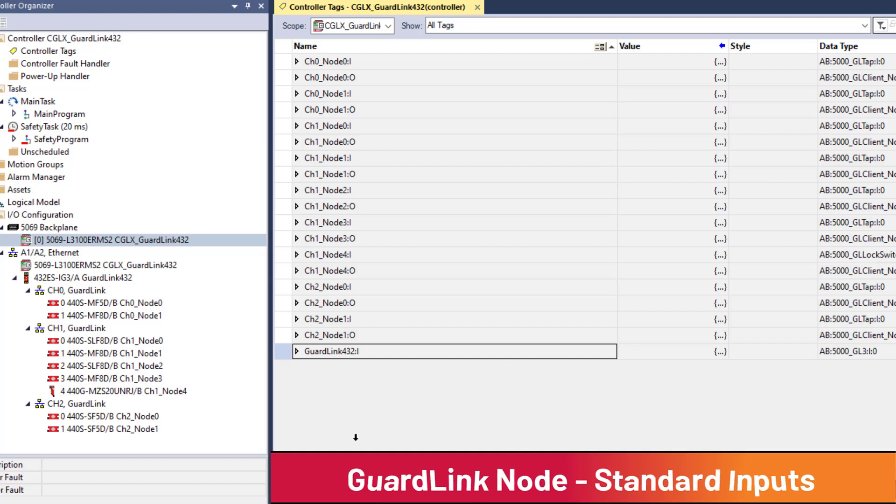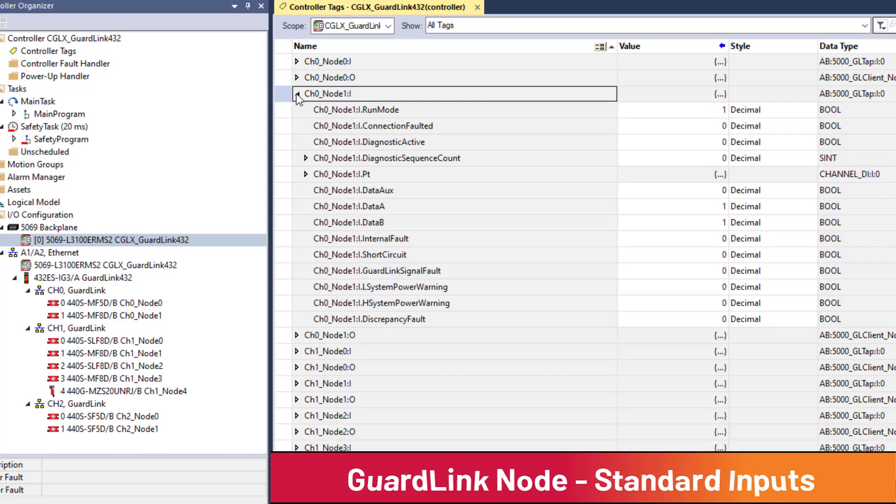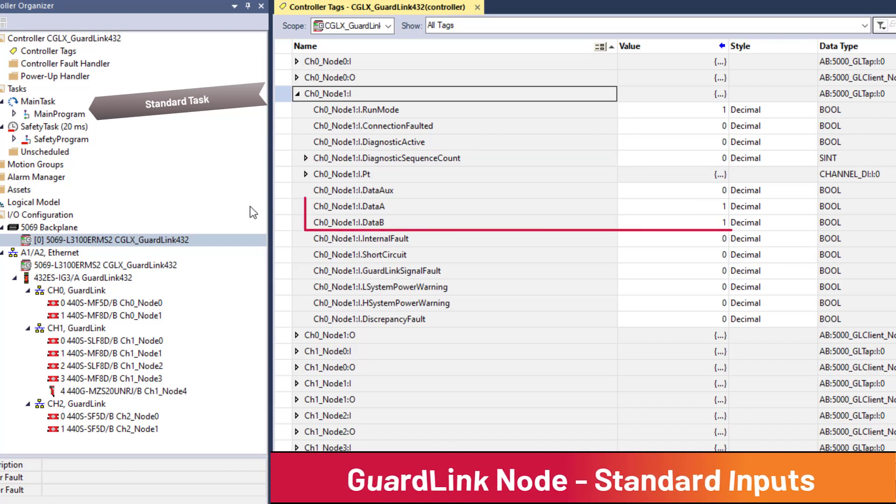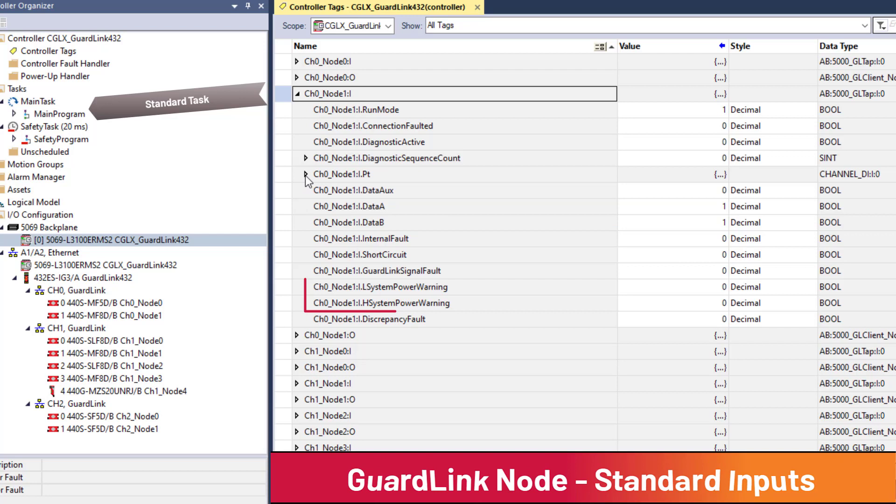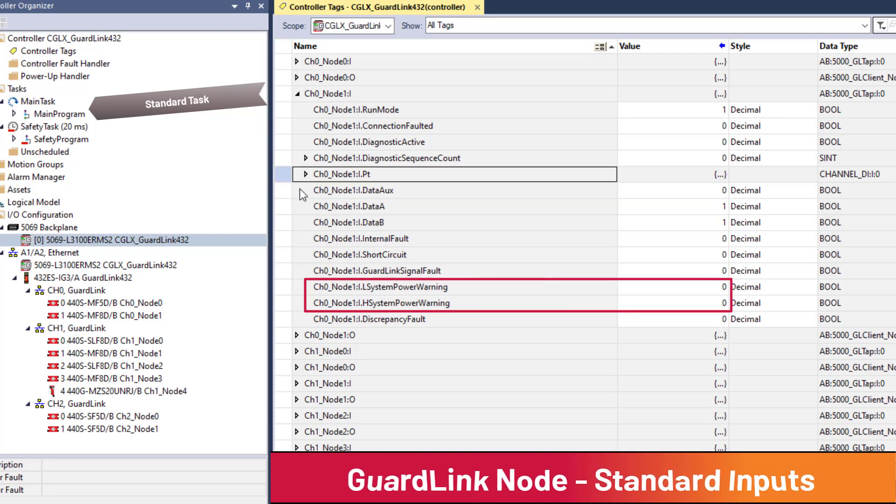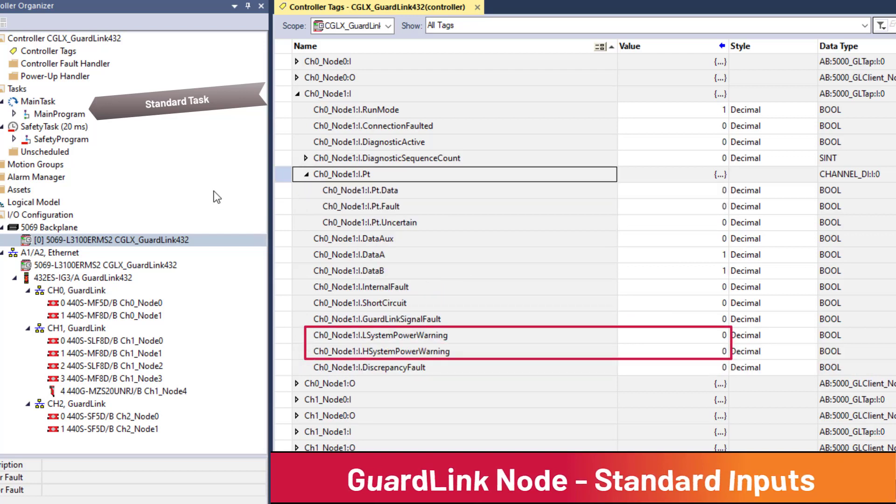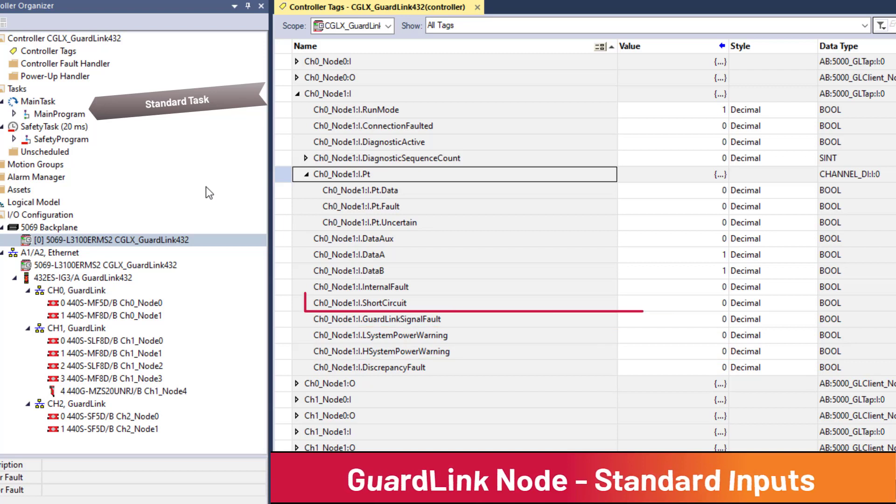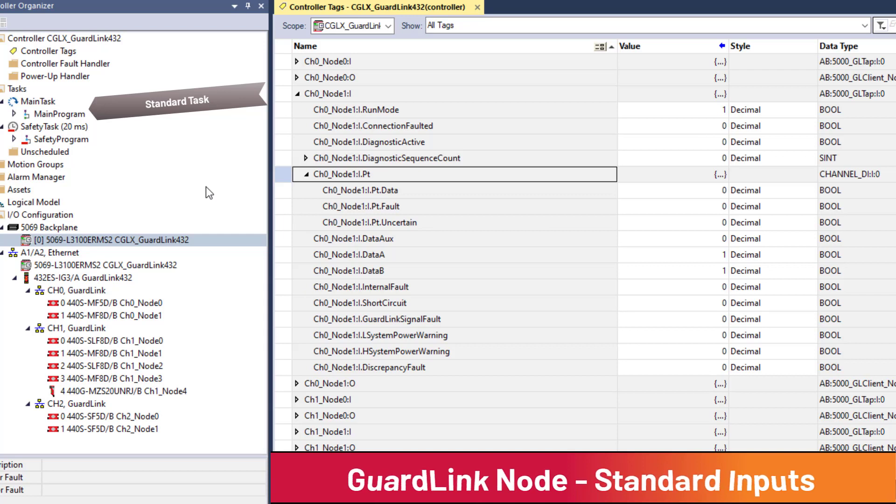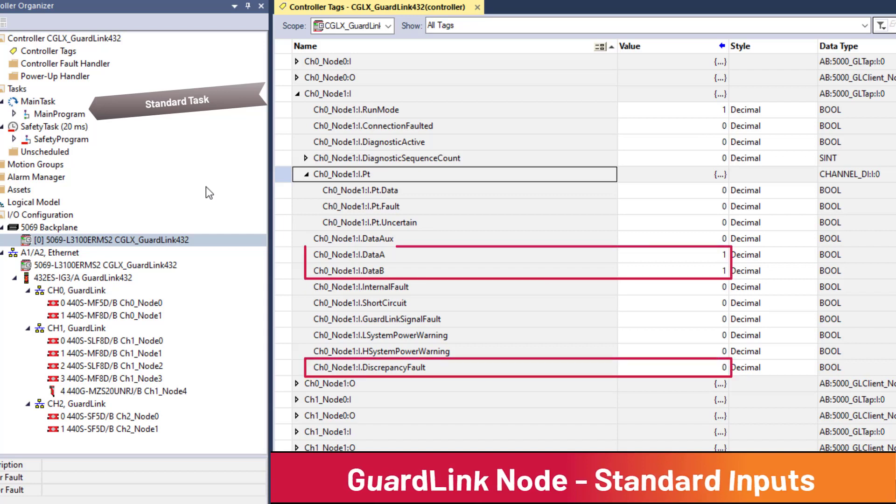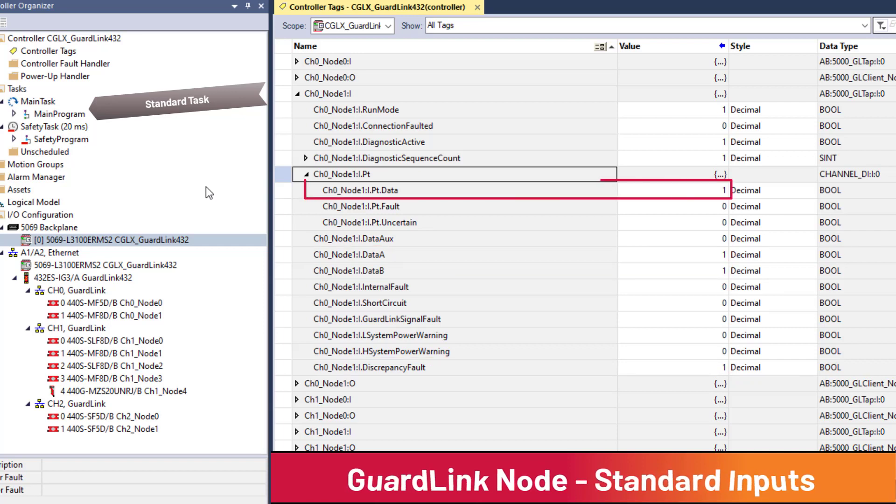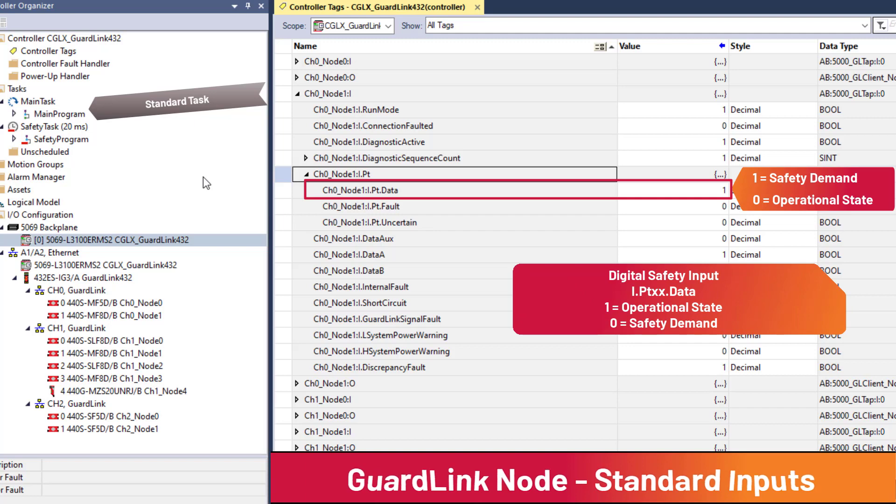Standard input data for a series B tap provides information such as diagnostic sequence count, which increments as node diagnostic events occur, channel A and channel B input raw data for dual channel devices, power warnings when supply voltage is outside the specified 20.4 to 26.4 volt DC range, short circuit for safety input shorts, and discrepancy fault when channel A and B are different. One item to note is i.point.data for a node indicates 1 when tripped. This is opposite state of digital safety input cards.